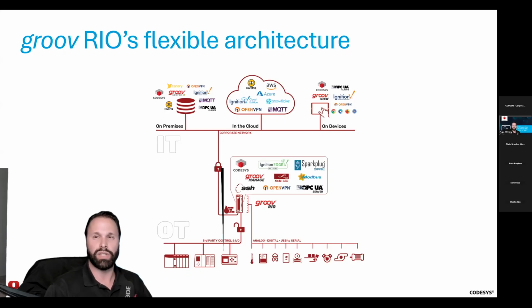In Point Energy's case, this is where they're bringing in their radar transmitters, pump controls, as well as some of those Modbus TCP and RTU communications. At the edge, this little device can run CODESYS for local control, and you've also got other tools like Node-RED for integration logic. It publishes data natively over MQTT Sparkplug. On the IT side, it safely and securely integrates with Ignition, cloud platforms like AWS, Azure, Snowflake, and supports cybersecurity tools including OpenVPN for secure remote access.